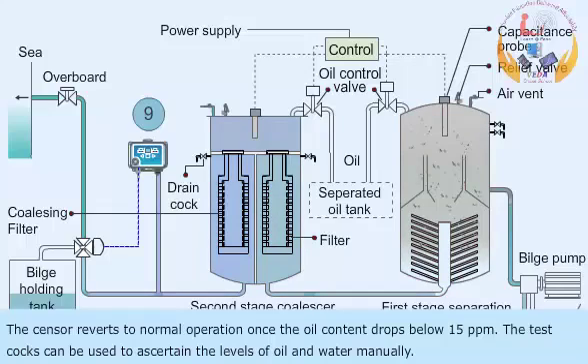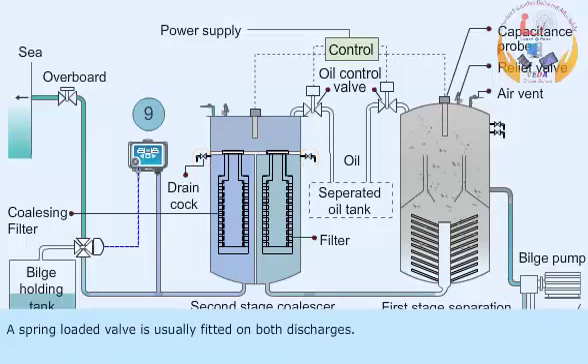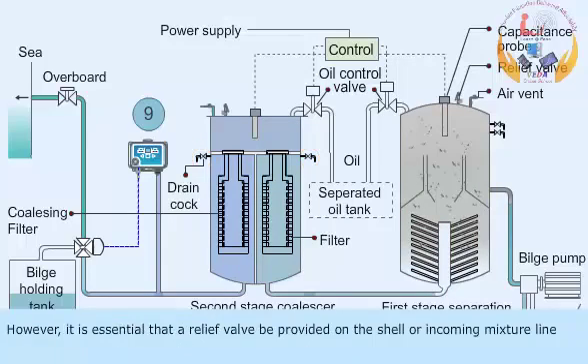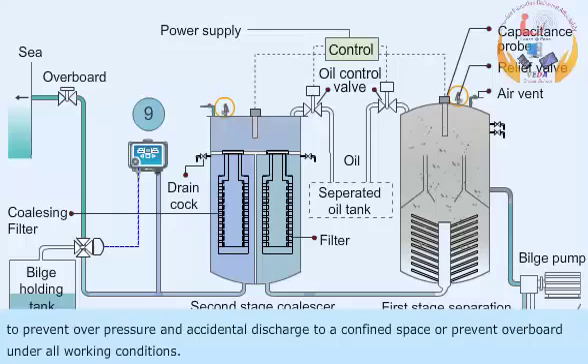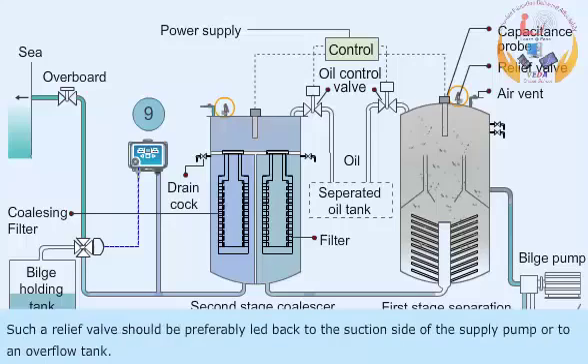The test cocks can be used to ascertain the levels of oil and water manually. A spring-loaded valve is usually fitted on both discharges. However, it is essential that a relief valve be provided on the shell or incoming mixture line to prevent overpressure and accidental discharge to a confined space, or to prevent overboard discharge under all working conditions. Such a relief valve should preferably be led back to the suction side of the supply pump or to an overflow tank.